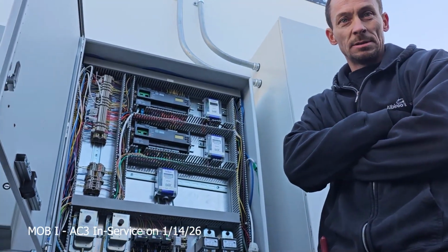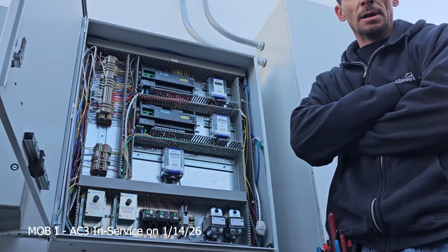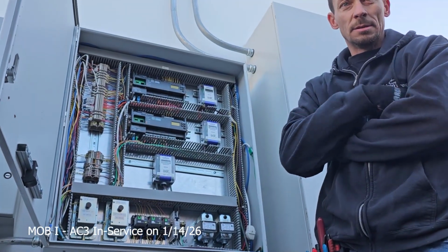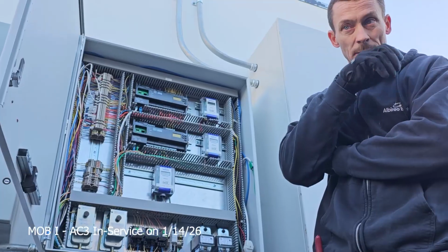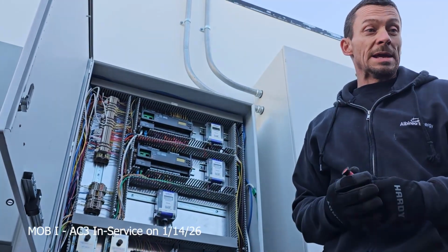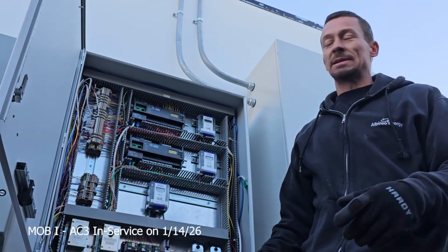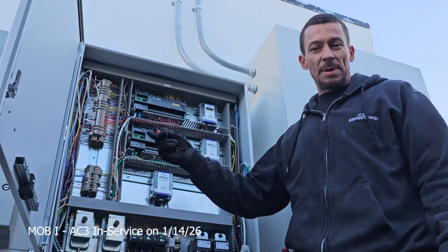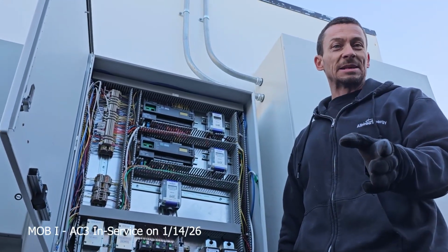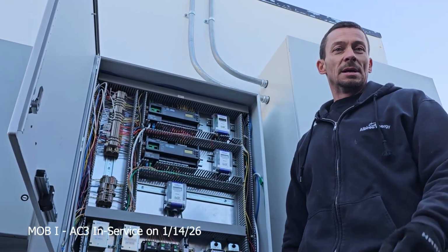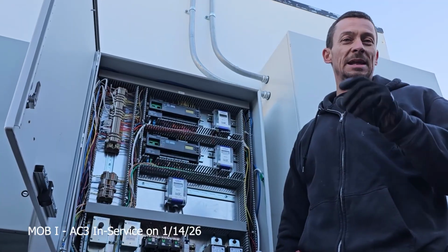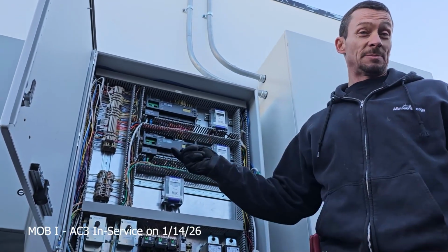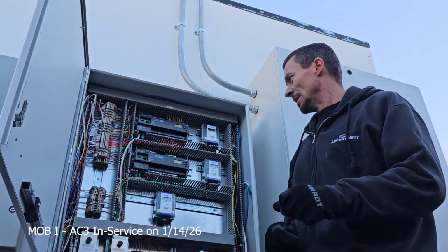If it goes, yeah, like this one up in the tower, all the air handlers have a switch that we can turn off and turn back on to reset. To reset the controller, you're talking about? Yeah. So sometimes, but that's more like for this, this is Ethernet. Back to the right. So you're saying for the MS, it's like MSTP over there, right? Yeah, probably. So sometimes that's just a little more finicky, and sometimes you need to cycle power. Sometimes it comes back online, sometimes it doesn't, depending on what happens.